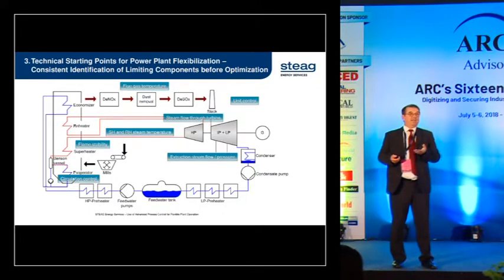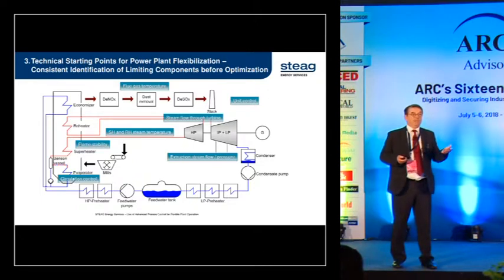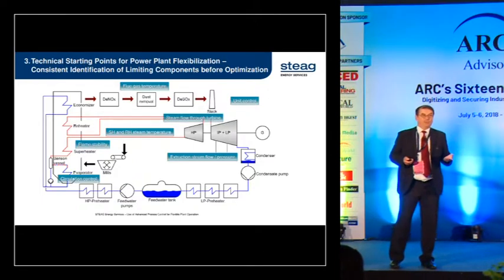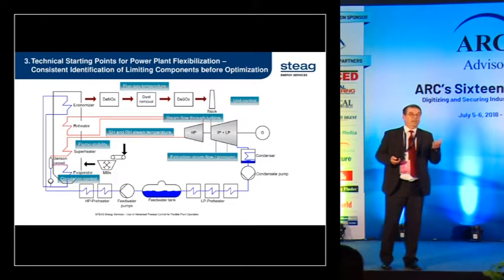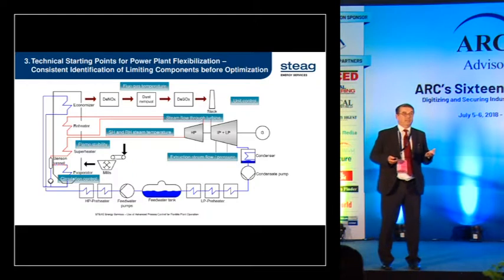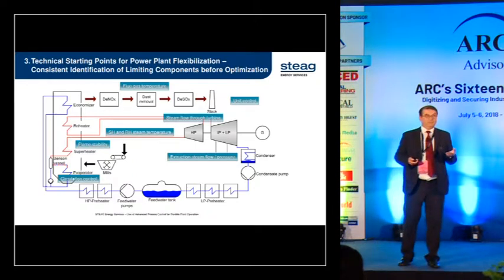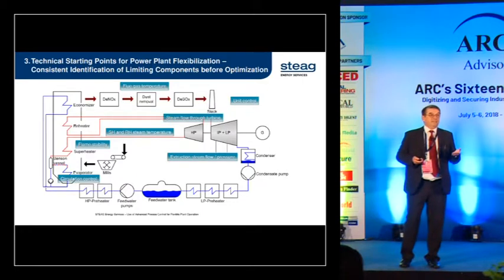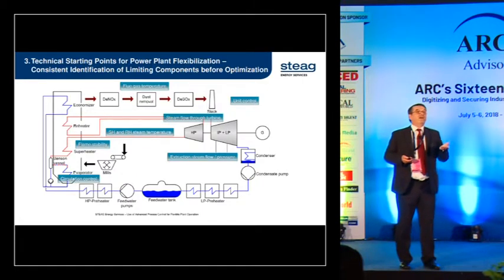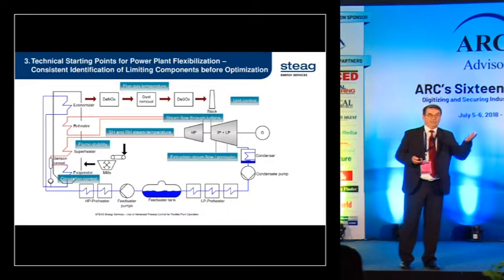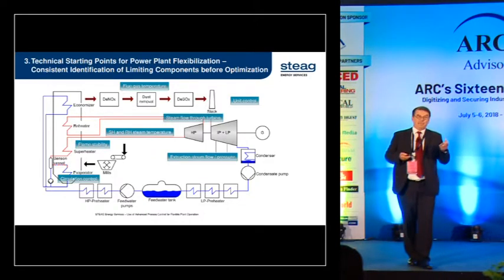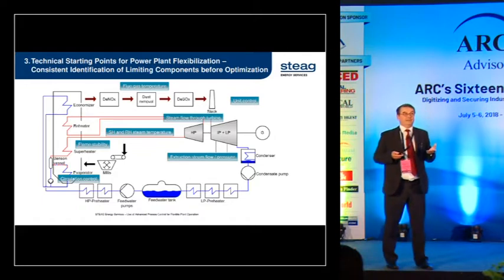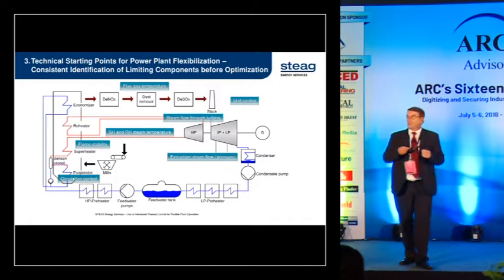One factor: the power plant runs at lower load. Operators try to keep the power plant at lower load because switching off, shutting down and starting up the power plant is very costly due to additional supportive fuel needed. The other factor: the power plant should react very fast to changing demand because of renewables - wind comes suddenly, sun comes. The prediction of these changes is getting better, but nevertheless the change in demand is very rapid, so we have to react very fast.